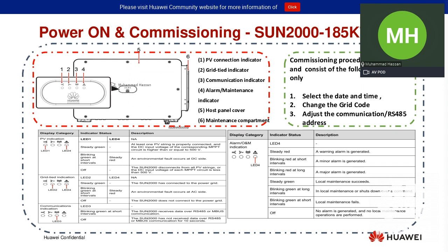The fifth part is called the host panel, which is also called the DC compartment. You are not allowed to open the DC compartment, because if you open it, we are not able to provide the warranty, as we cannot control the environmental conditions when it is opened. This compartment was sealed under a clean and properly controlled environment to provide the best performance and output for the lifetime of that inverter. The sixth part, as mentioned before, is the maintenance compartment or the AC compartment. You are only allowed to install the AC cables or the tracker cables in the AC compartment.